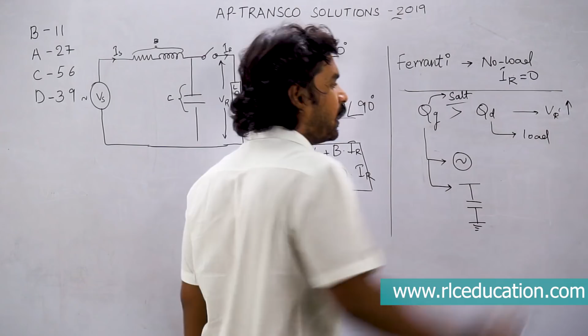Whenever voltage at any particular bus or substation falls, what do we do? Generally we connect capacitors. What is a capacitor? A source of reactive power. Injecting reactive power means you are improving the voltage. That is what reactive power management means.